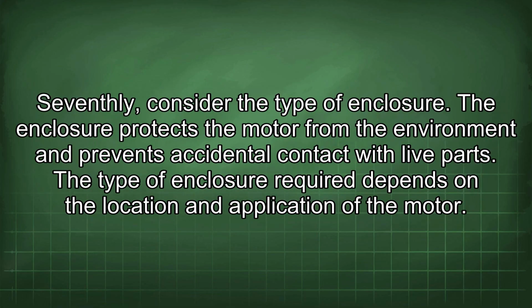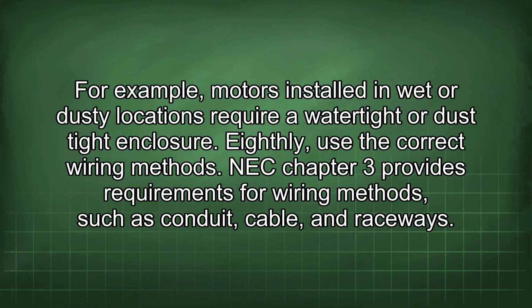Seventhly, consider the type of enclosure. The enclosure protects the motor from the environment and prevents accidental contact with live parts. The type of enclosure required depends on the location and application of the motor. For example, motors installed in wet or dusty locations require a watertight or dust-tight enclosure.